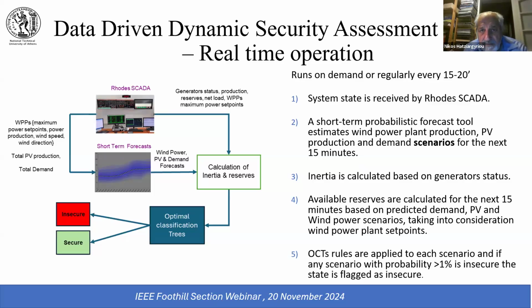The dynamic security assessment runs every 15-20 minutes. It receives the system state from the SCADA system of the island, then estimates what the dynamic security will be in the next 15 minutes by running a short-term probabilistic forecast of wind power, PV production, and demand, creating a number of scenarios for that period.